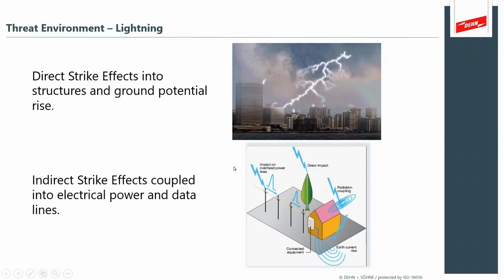That's in relation to an indirect strike, where you got struck but it's the building next to you, so you only indirectly experience the ground potential rise, or only the electromagnetic effect where it's coupling into the wire. It doesn't have to strike the wire for it to still induce surges. And it can come from far away, and those are considered indirect, but there's still lots of energy in what you would call an indirect strike.